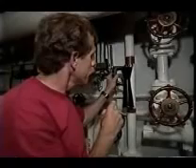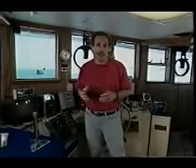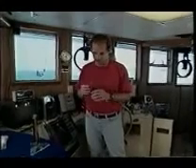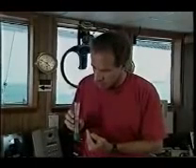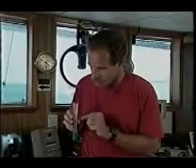Another type of device which uses blockage to measure flow rate is the variable area flow meter, sometimes called a rotameter. What this consists of is a tapered tube with a float in the tube. The flow causes a pressure force on the float, which is balanced by the gravitational force. Now we looked at several variable area flow meters when we were at the Omega Engineering Labs.